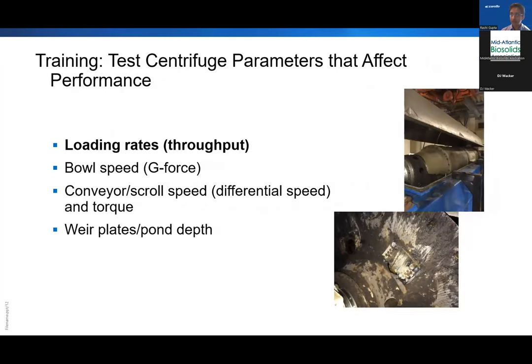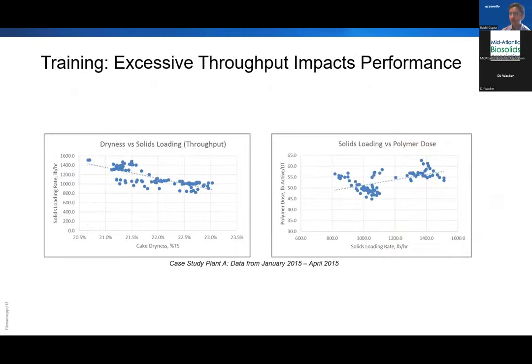Continuing on with the training, we talked and went through the importance of different centrifuge operating parameters that can impact performance, with the focus being on loading rates, so the throughput through the machines. We also talked about all the other things we typically look at when we're optimizing: the bowl speed, the conveyor speed and torque, the placement of the weir depths for the pond depth inside the machine. But the loading rates are very critical, and it's important for everyone to track that, which goes back to what Tony was talking about related to the changes in the sludge characteristics and how that has an impact on what you're actually pushing through the machine.